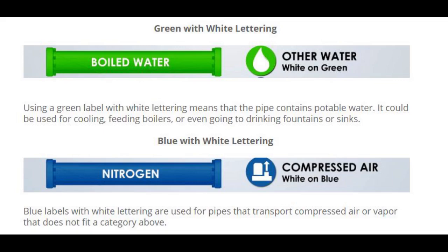Green with white lettering: Using a green label with white lettering means that the pipe contains potable water. It could be used for cooling, feeding boilers, or even going to drinking fountains or sinks.